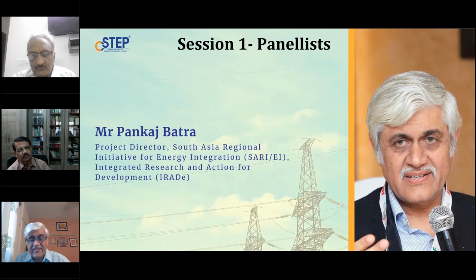If you reduce the efficiency and underutilize that plant, bringing it down to 50%, your fixed charges remain the same. So if instead of 80 or 90% you bring it down to 50%, it's almost like doubling the fixed charge, which would otherwise come to maybe around 1 rupee 50 paisa per unit for a new plant. It will double to 3 rupees per unit, fixed charge only. So you have to look at it from that point of view.